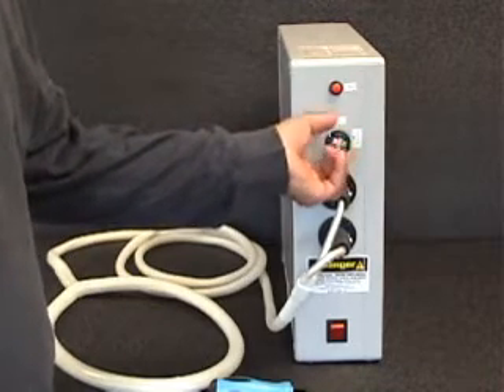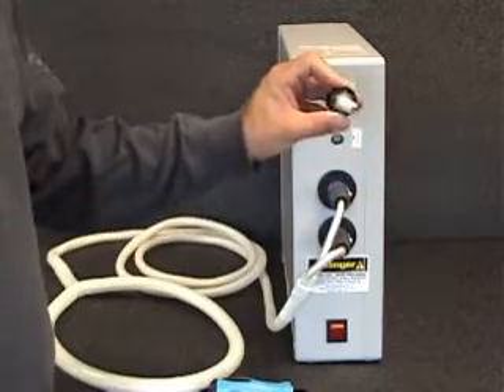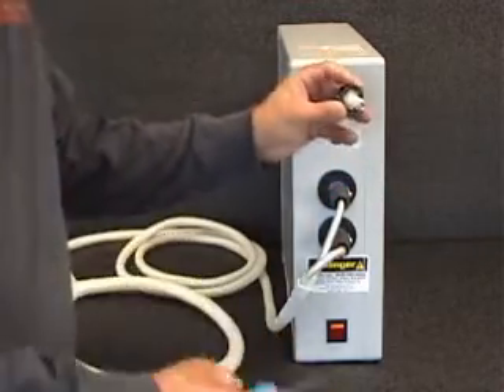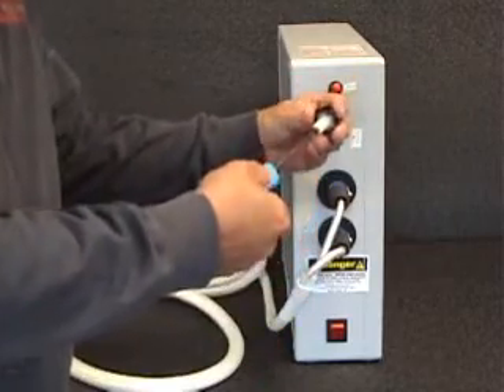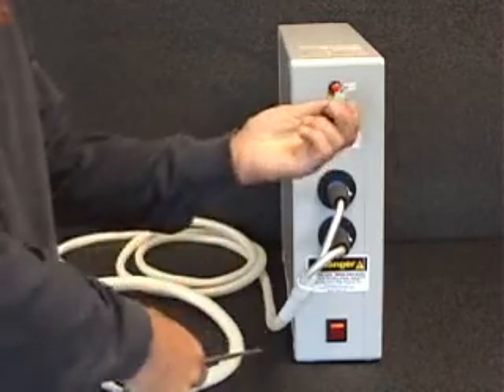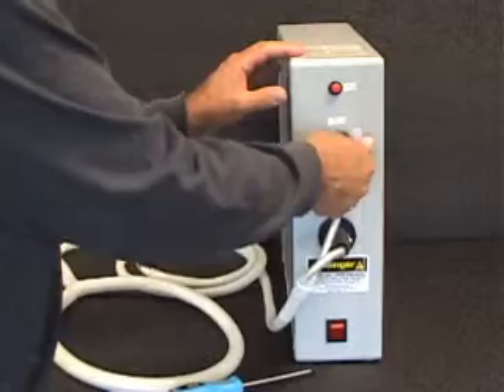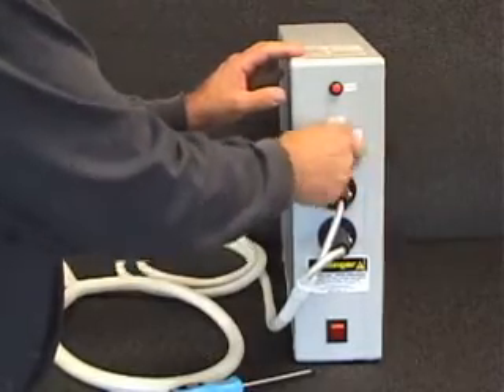In the back side of the intensity control knob is a Phillips screw. Rotate this screw counter-clockwise approximately one turn, and then put it back into the position and rotate it clockwise to screw it in until it reaches a minimum position.